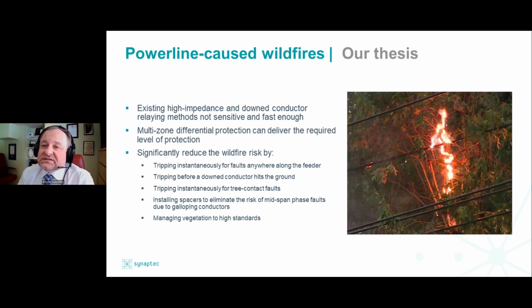So our thesis is that we cannot trust the high impedance and down conductor relaying methods at the substations. They're not sensitive enough and they're not fast enough. Those of you who tried those relays know that they may take tens of seconds and longer to detect a high impedance fault or down conductor. From our experience in transmission systems, we know that multi-zone differential protection can deliver the required level of protection. And I will explain what multi-zone means.